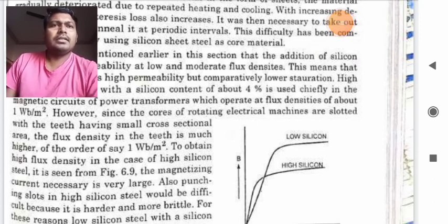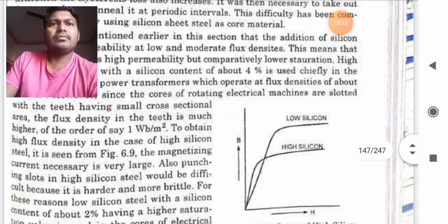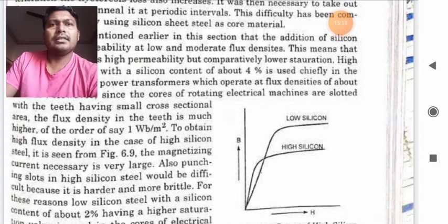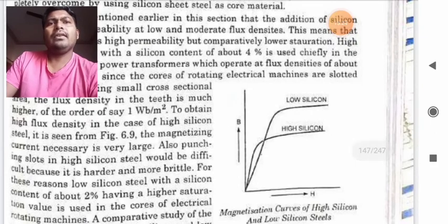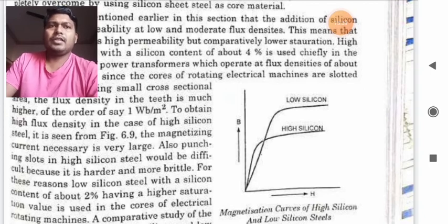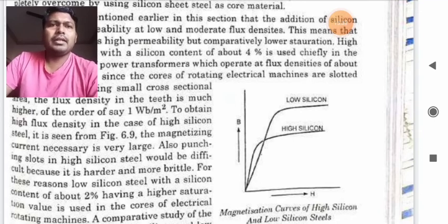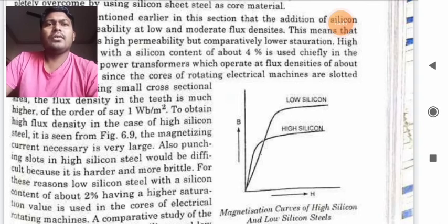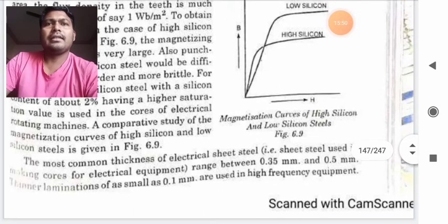However, since the cores of rotating electrical machines are slotted with the teeth having small cross section area, the flux density in the teeth is much higher. To obtain high flux density in the case of silicon steel, the magnetizing current necessary is very large. Also, punching slot in high silicon steel would be difficult because it is harder and more brittle. For these reasons, low silicon steel with a silicon content of about 2% having higher saturation value is used in a core of electrical rotating machines.